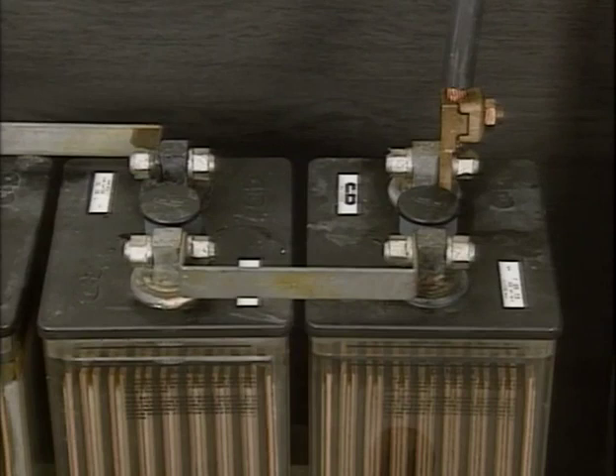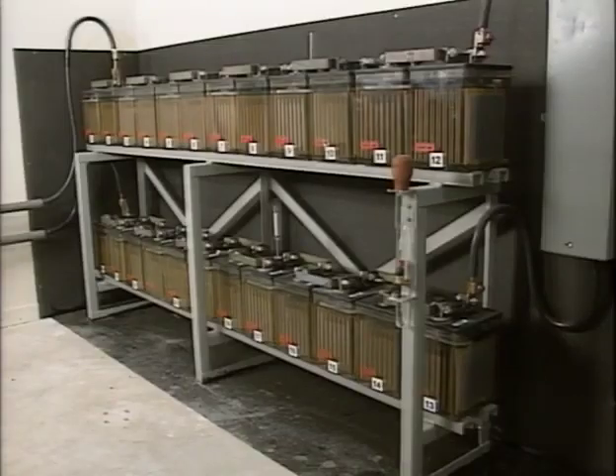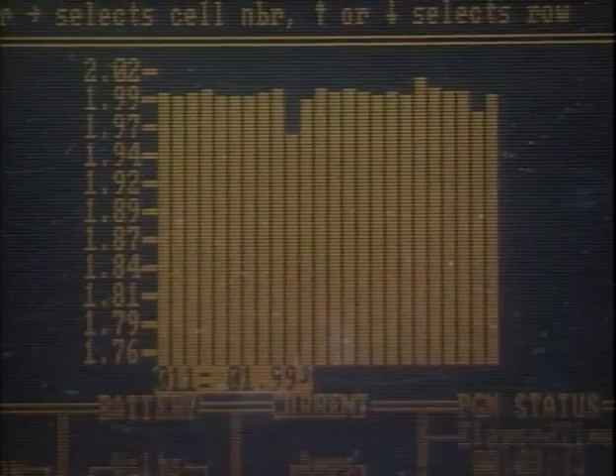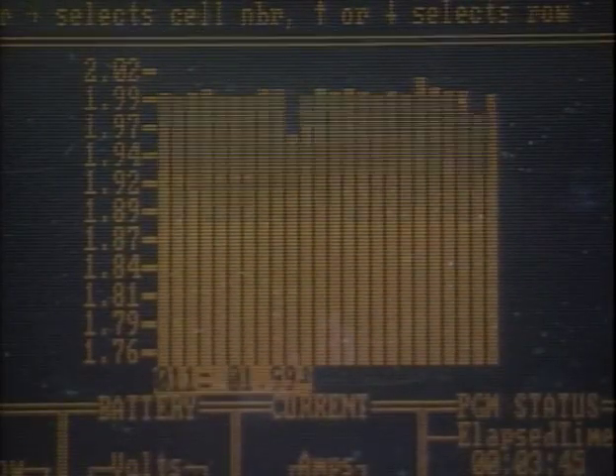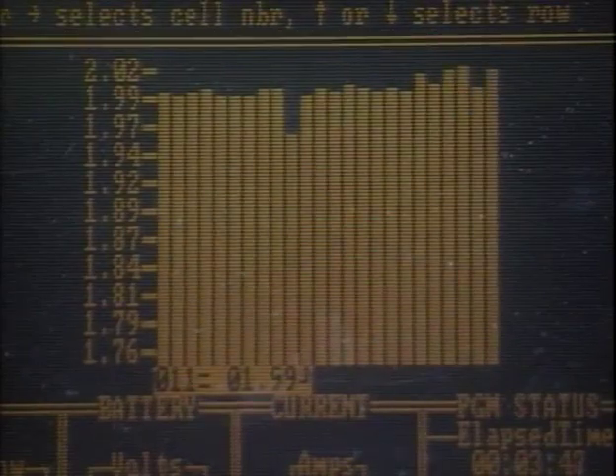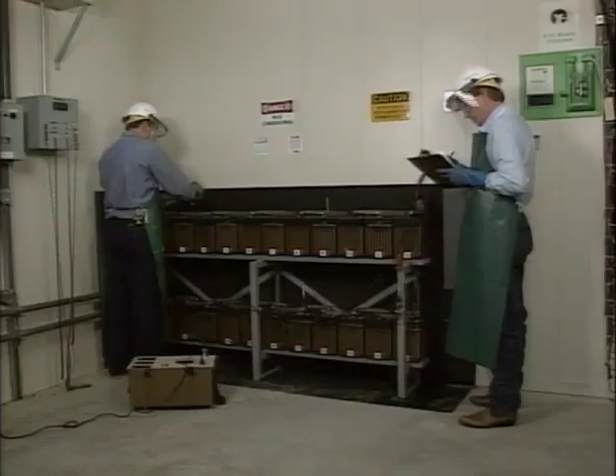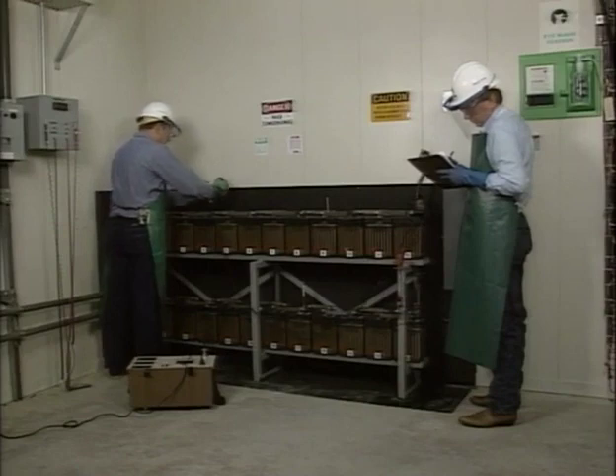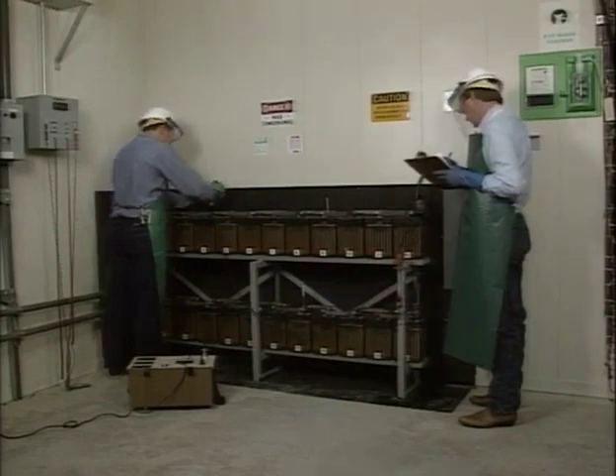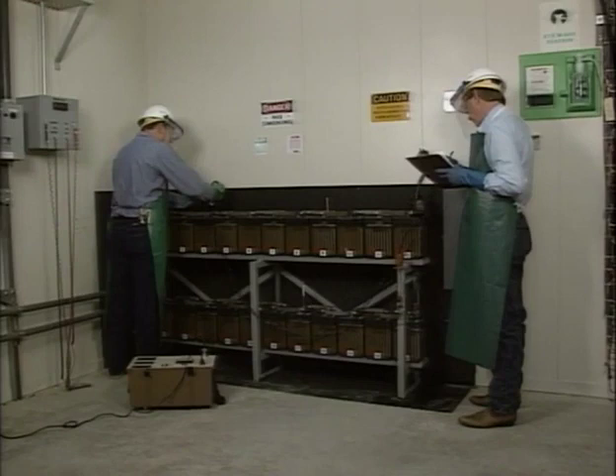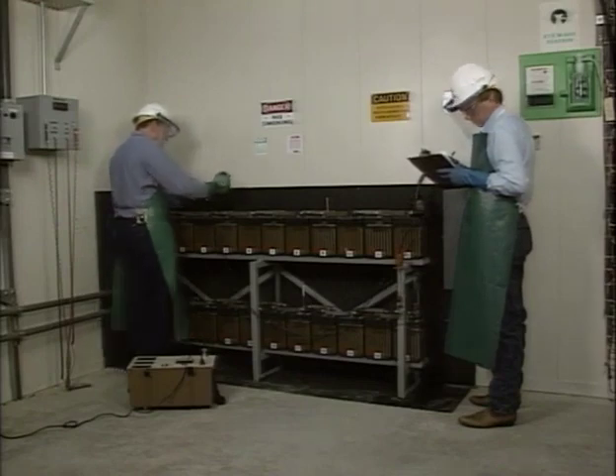As we saw in this part of the program, integrity testing identifies problems in the battery's connections and intercell conductors, and capacity testing determines the remaining useful life of the battery. Both tests help indicate if the battery can deliver the necessary power when it's needed. However, repeated capacity testing can shorten the life of the battery, so it's only done about every 5 years. Between capacity tests, the remaining life of the battery can be checked with another test called the impedance test. Impedance testing will be described in the next part of this program.